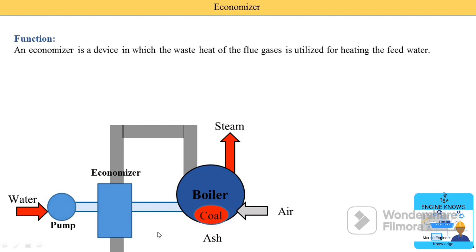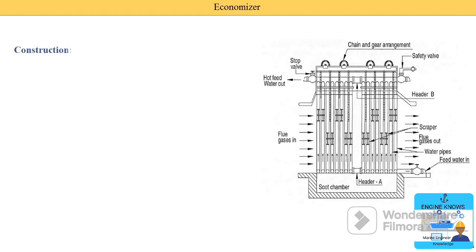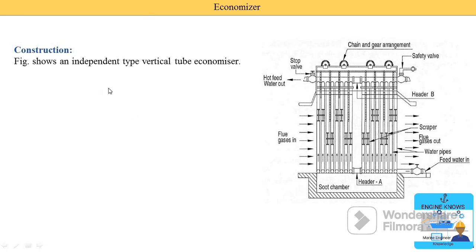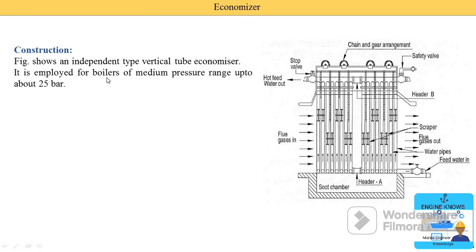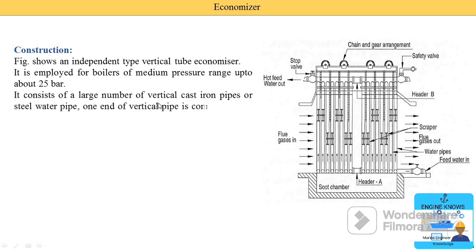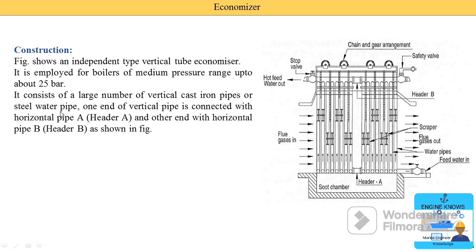Next we move towards the construction. This is the image of the independent type vertical tube economizer. There are a number of vertical tubes. It is employed for a boiler of medium pressure range up to 25 bar. It consists of a large number of vertical tubes, and the material of these tubes is either cast iron or steel.